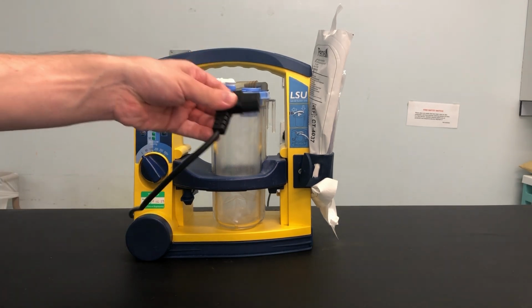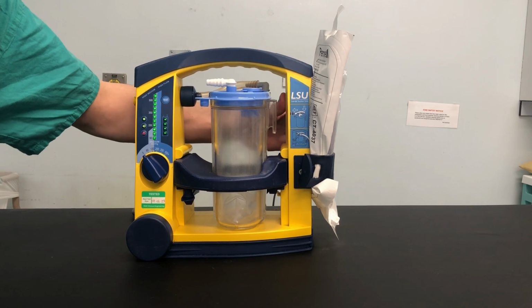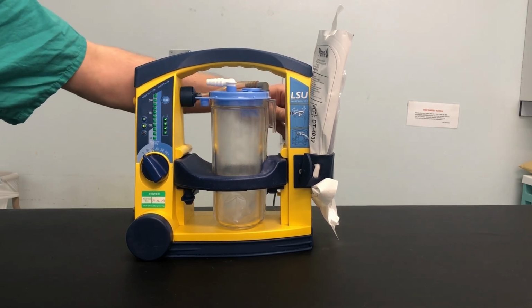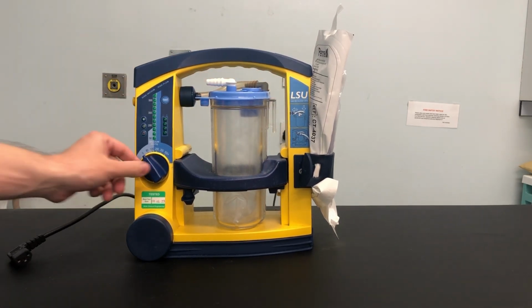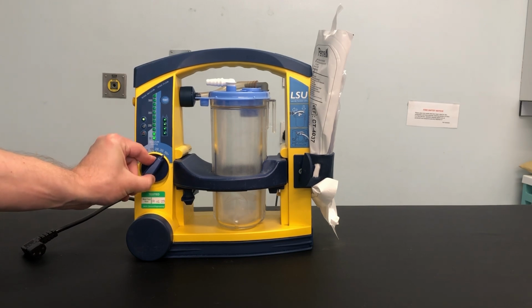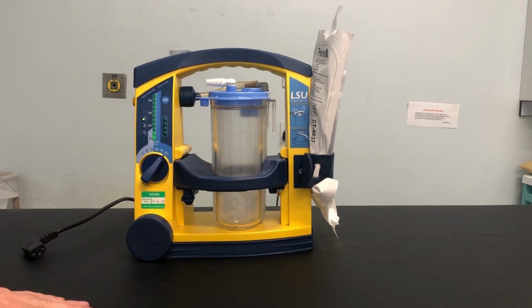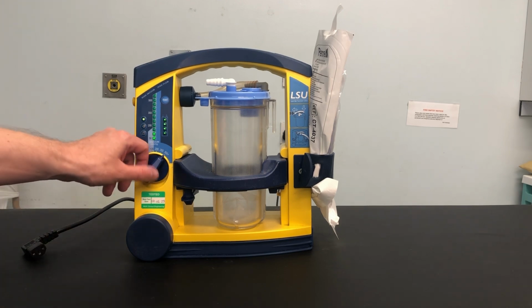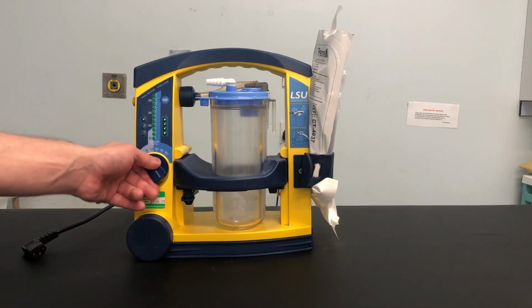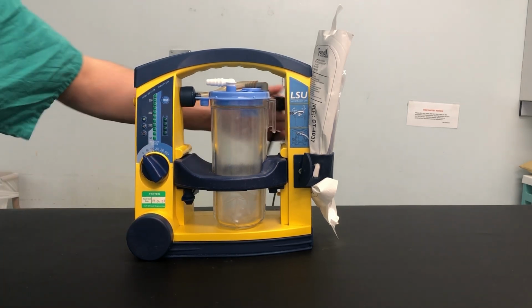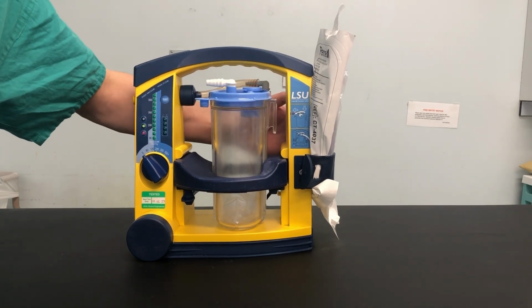If all 4 battery lights are not lit when they stop flashing, plug the device in for 3 hours and then repeat the test. If after charging the device for 3 hours and repeating the battery test, all 4 lights are not lit, remove the device from use. Complete a clinical engineering decontamination form detailing any error codes or messages and return to MESU for repair or service.